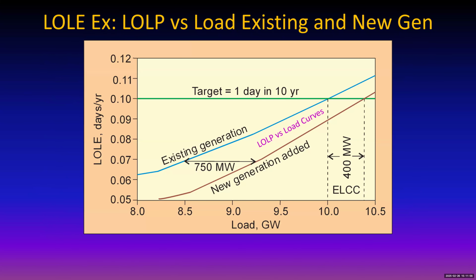If the target is 1 day in 10 years for the LOLE, that's 0.1 day in 1 year. Let's say the existing generation is represented by the blue line, generating at 8 gigawatts, below its full capacity. Then the LOLE is about 0.062 or 0.063, somewhere in that neighborhood. Notice that as you increase the load on that generation, the likelihood that it's going to go down increases.